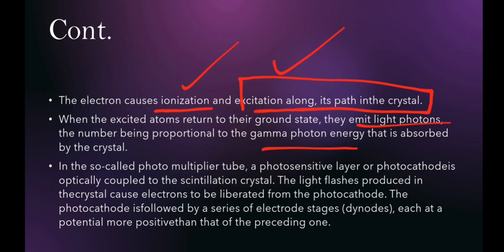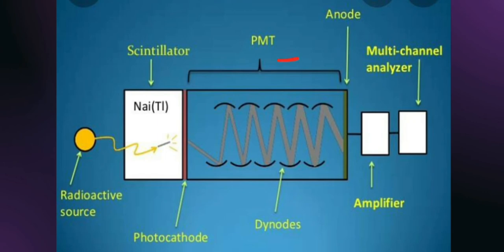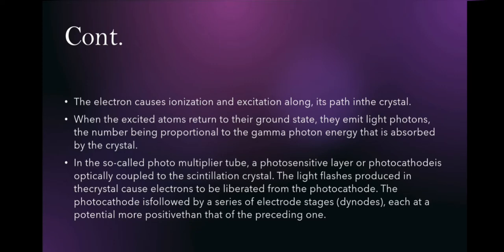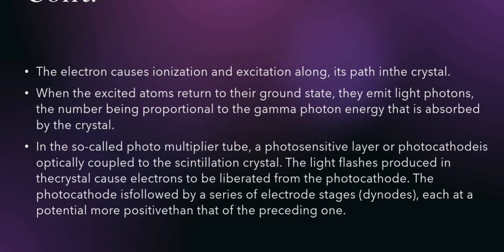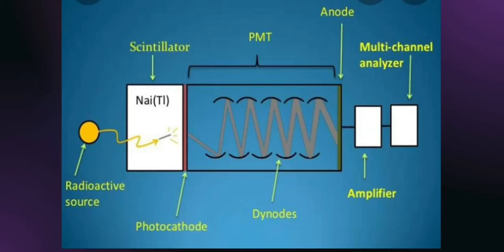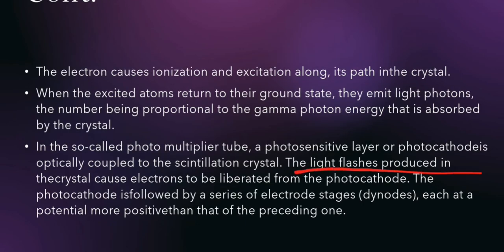In the so-called photomultiplier tube, as you can see here, what we have is this PMT — the photomultiplier tube. A photosensitive layer or photocathode is optically coupled to the scintillation crystal. This cathode is further attached to the scintillation crystal, and the light flash produced in the crystal causes electrons to be liberated from the photocathode.